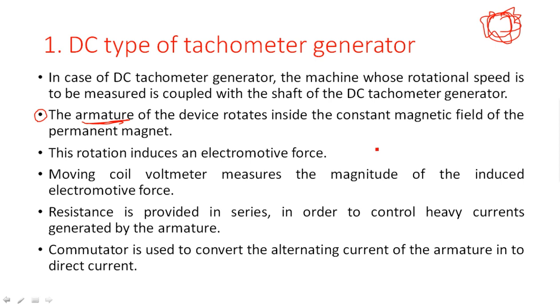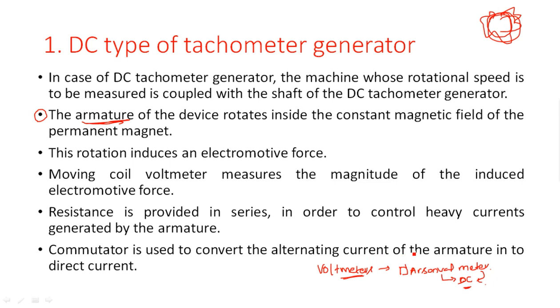A commutator is used to convert the alternating current of the armature into direct current. The D'Arsonval meter — used in voltmeters — works only with DC current, not AC. Since the armature movement generates AC, that alternating current must be converted to DC for the voltmeter to work. Therefore, a commutator is used in the DC type tachometer to convert AC to DC, so the armature output voltage can be measured by the voltmeter.